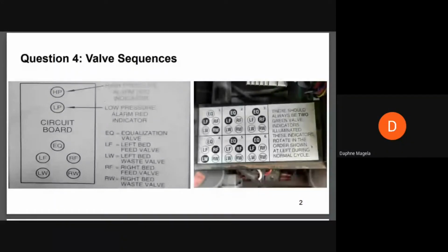Thanks, Maui. So it is true that some models of oxygen concentrators have an equalizer valve. To understand the purpose of the equalizer valve, we have to go through the cycles of the AirSep Intensity model. The AirSep model has 5 valves: the equalization valve, the left feed valve, the left waste valve, the right feed valve, and the right waste valve.